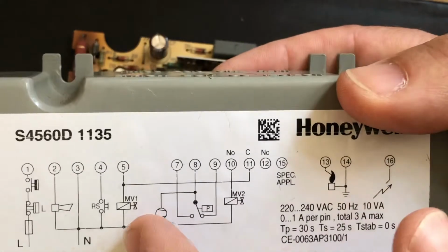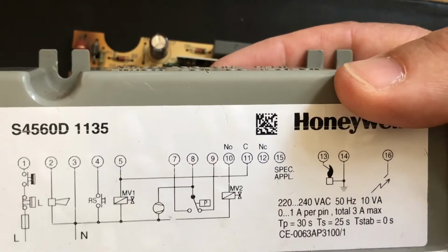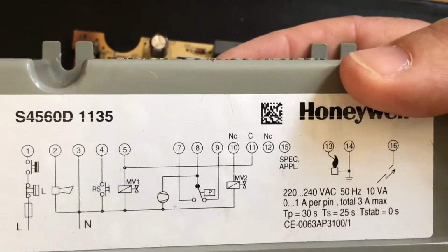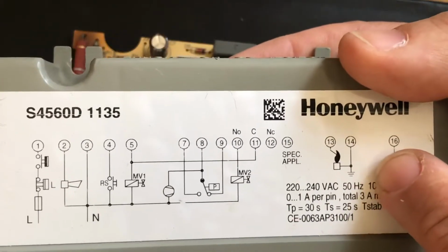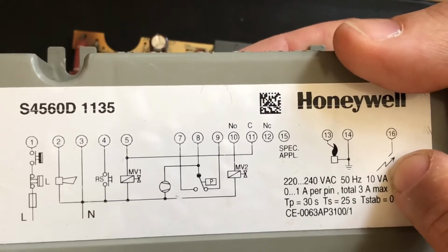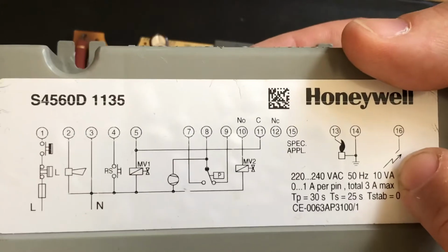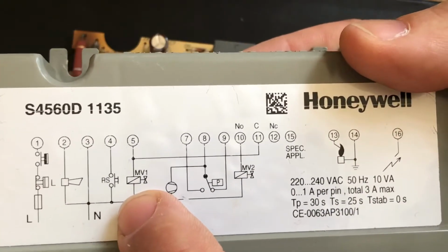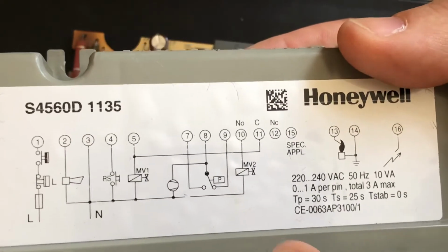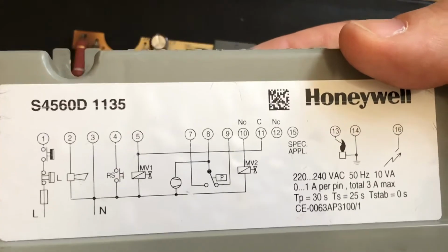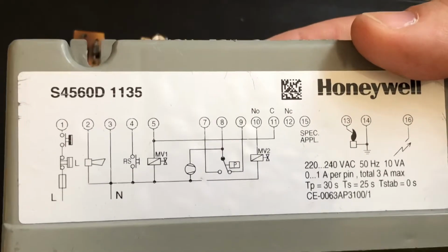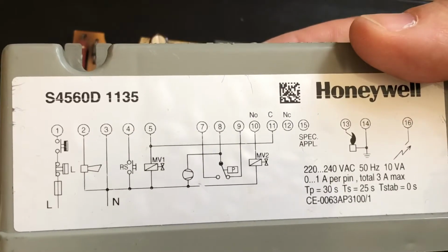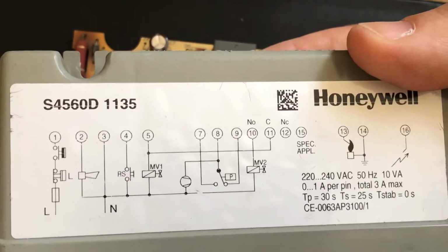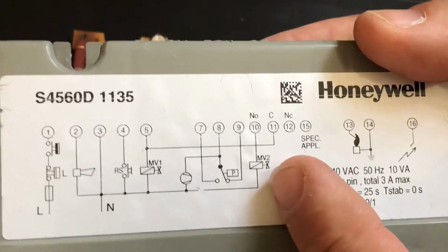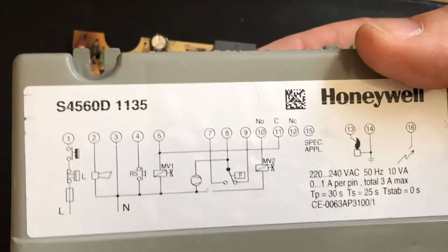But this is done only to check if it's healthy. So if it's healthy, once the fan starts, this switch will close the circuit between 7 and 8. You have to wait for 30 seconds, and then the spark plug will be initiated. You will hear the noise, zzz, zzz, zzz. And if you have a pilot flame, then the valve MV1 will open and allow the gas to go via the pilot flame, which will send the signal to the ionization probe. Once the signal is sent to the ionization probe, it will open the secondary valve, which is MV2, and you have the main flame, and the boiler will work.